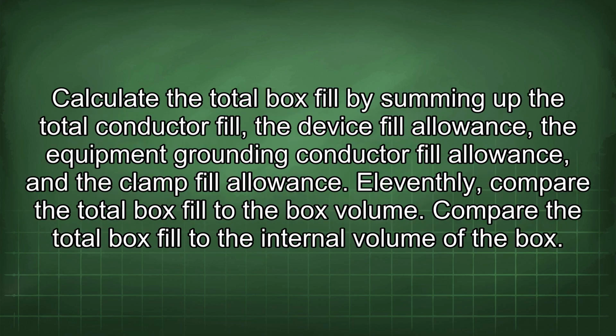Tenthly, calculate the total box fill. Calculate the total box fill by summing up the total conductor fill, the device fill allowance, the equipment grounding conductor fill allowance, and the clamp fill allowance.